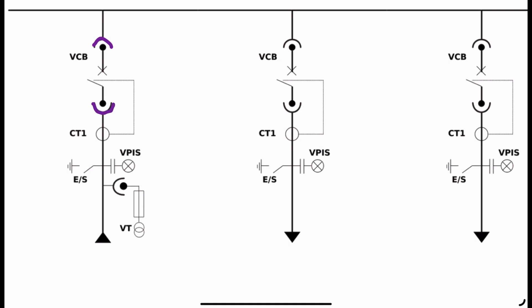Since it is a withdrawable-type circuit breaker, it can be removed whenever necessary — for example during maintenance. This is also the reason why you will find there is no disconnector used in this single line diagram. When you remove the withdrawable circuit breaker, you have a visible isolation that the human eye can see — and that is why a disconnector is not necessary. But if it were a fixed-type circuit breaker, it would be good to have a disconnector for visible isolation.